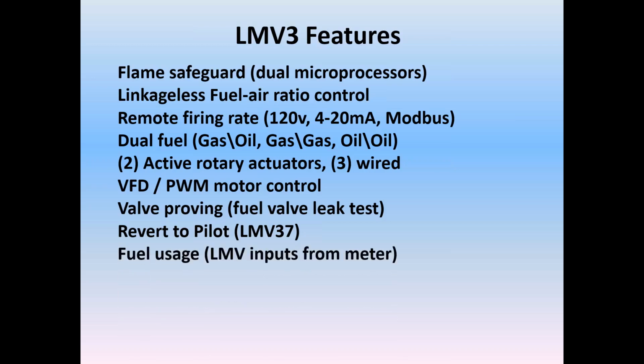Fuel usage: there's inputs on the LMV that can take pulses from fuel meters. So now you can read the fuel usage on the AZL display. You can bring it to a touchscreen, or you can bring it to a BMS or automation. It's available as a Modbus point. And it has a Modbus feature. You simply take the LMV3 and add the OCI module, and then you can do Modbus communication.